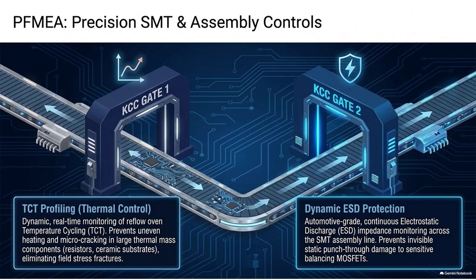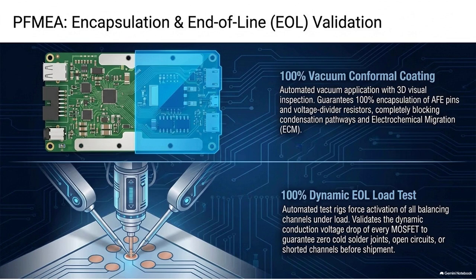And during active charging, it shifts to testing the dynamic leakage current, injecting a test current, measuring the voltage drop, making sure the resistance isn't infinite, which would confirm the open circuit failure. Yeah. It is constantly mapping the health of every single balancing component.